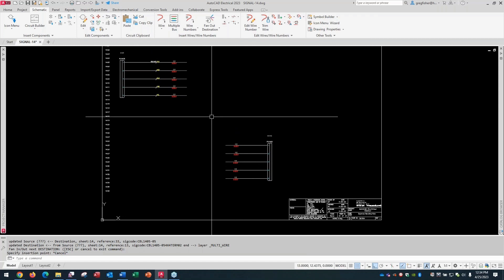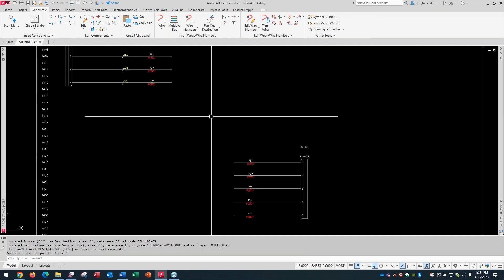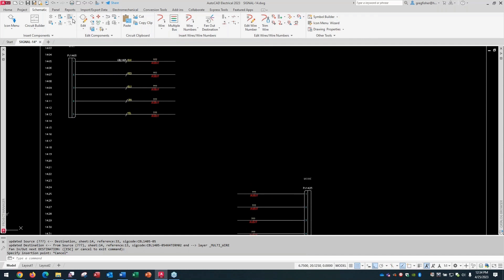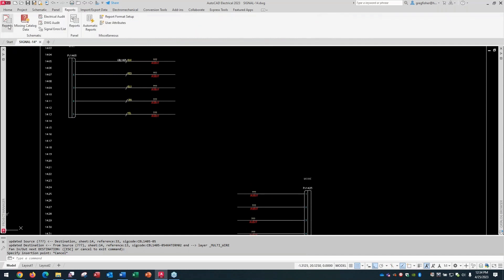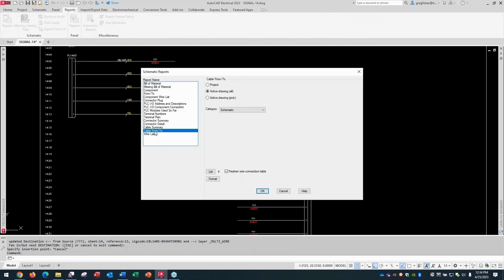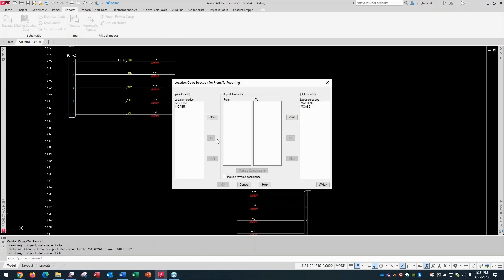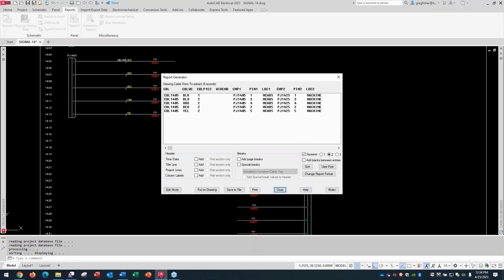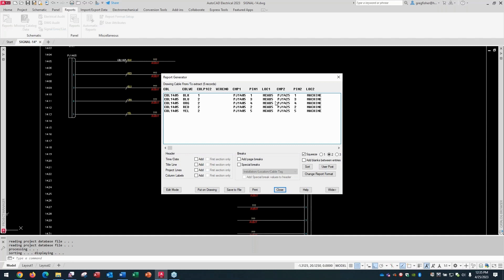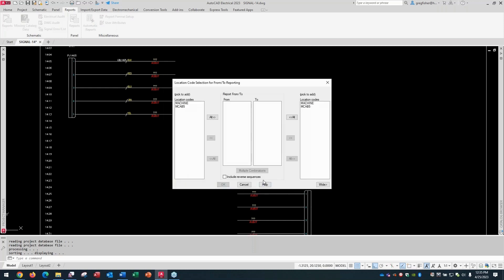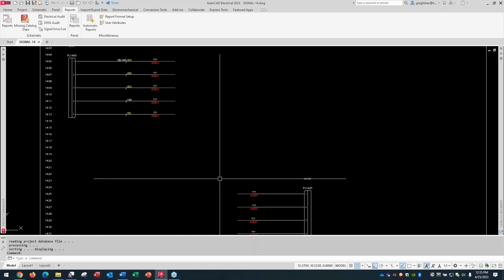If I go to my reports, and I go to cable from/to for the active drawing, to all locations, it already works perfect from a source destination standpoint. Now, these got out of order for some reason, that's an easy fix, but you can see that cable 1405 black coming from pin one of this connector going to pin one of this connector. Same thing with the rest of them. So if I didn't do anything else, and I ran a report on this, it already works perfect, as far as the source destination is concerned.